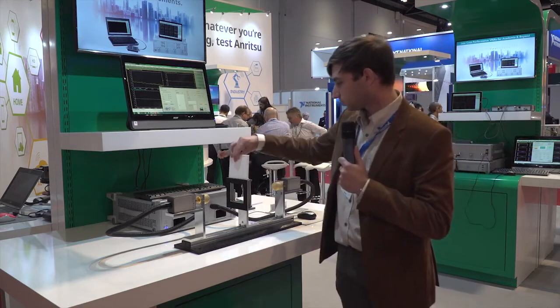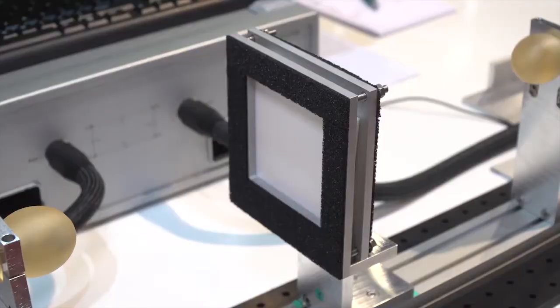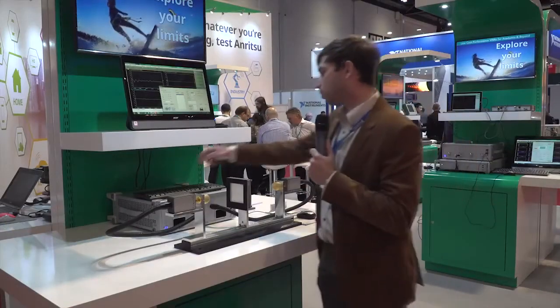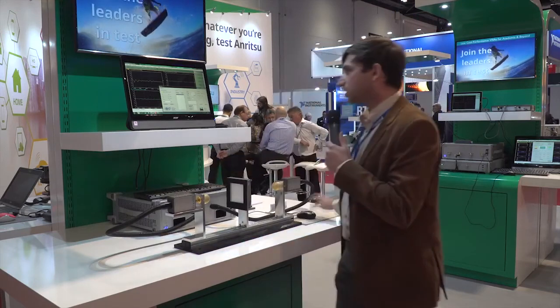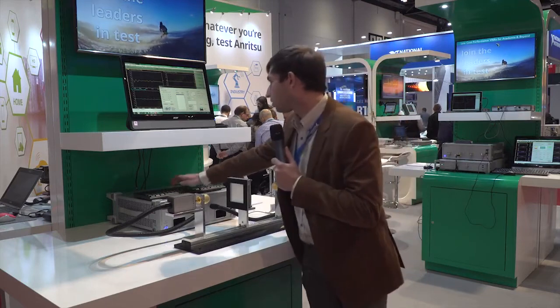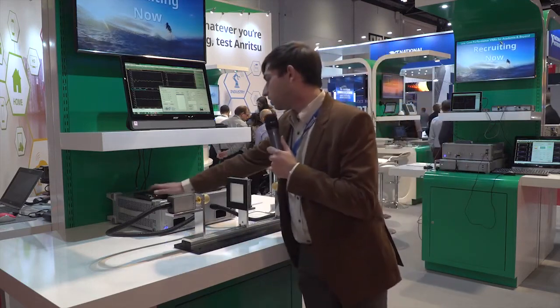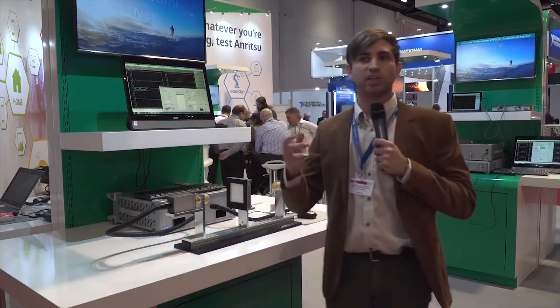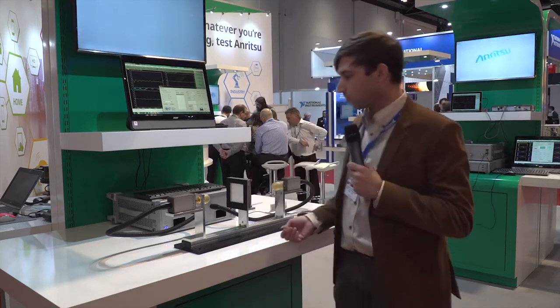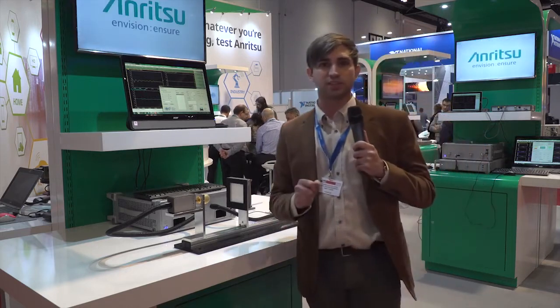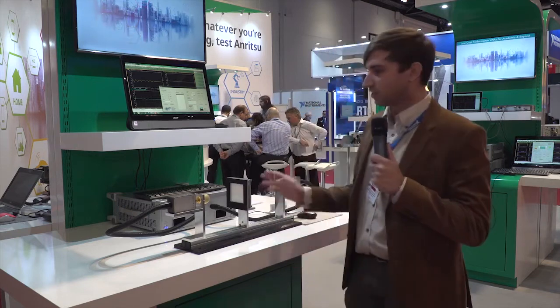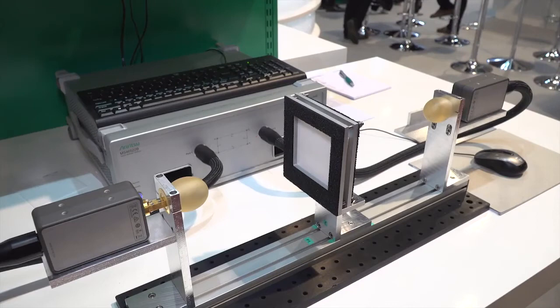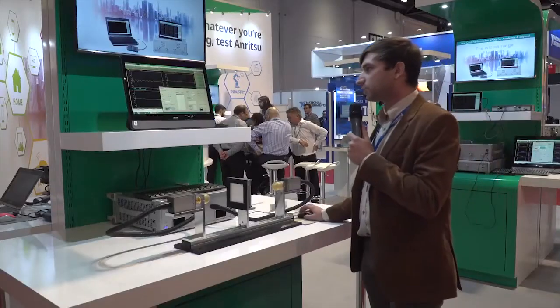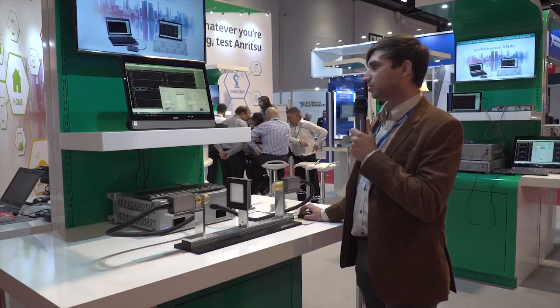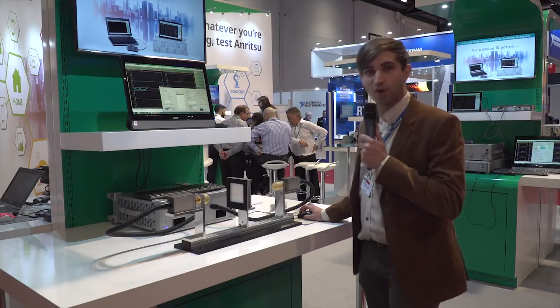8 millimeters thick. Clicking on measure, we have the sample here in the interface. We put the name, Teflon, the thickness that must be known, 8 millimeters, and the value that we expect it to have. This is a starting point for the iterative algorithm that we apply afterwards. Teflon is a very well-known material because the dielectric constant stays almost at 2.1 for the whole frequency range up to a very, very high frequency. Of course, at 77 gigahertz it will sink a little bit, but it will still be very close to 2.1. So I just write 2.1 as the starting point. Then I press measure, and the measurement is ready already.